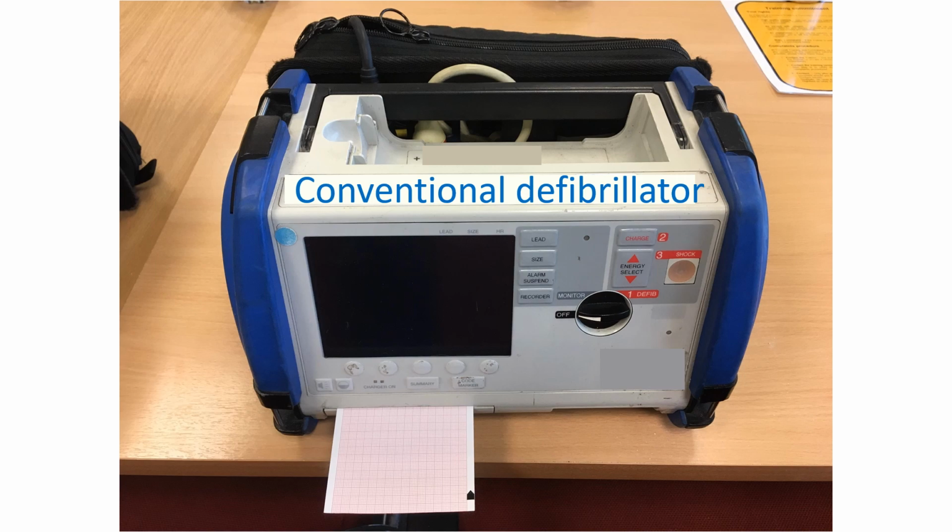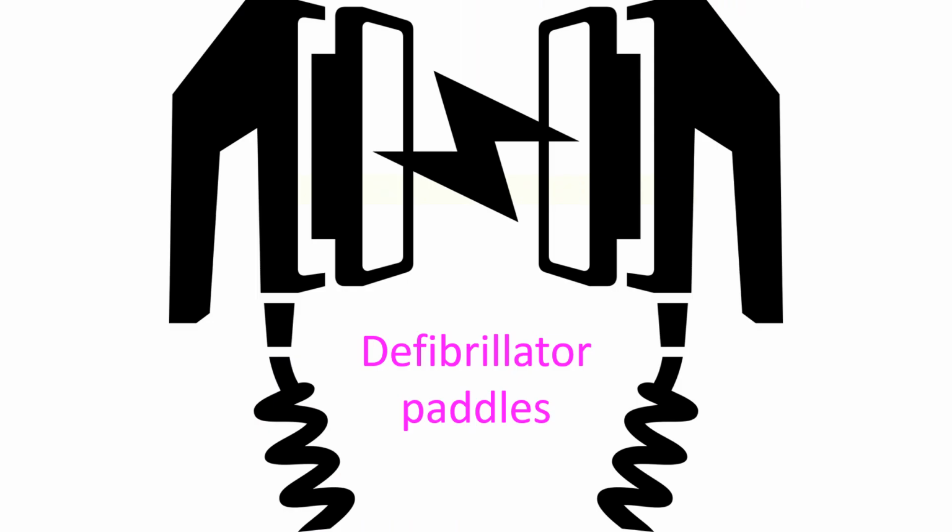In a conventional defibrillator, as automatic rhythm analysis is not available, the trained operator has to decide whether a shock is advisable or not. But most modern defibrillators also have an AED mode for emergency use. Proper application of patches or paddles is necessary. If paddles are being used, an adequate amount of conducting gel has to be applied over them for proper delivery of shock. Paddles should be firmly applied for the same purpose as well as to minimize skin burns.